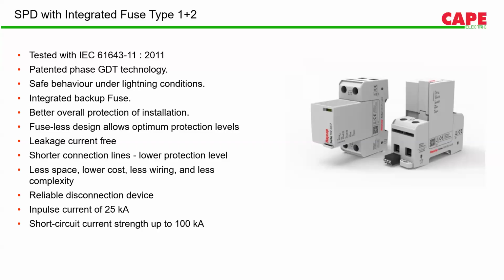That means if we are installing an SPD in the main incomer panel, let's say a 4000 ampere panel, with a fault current rating of 65 kiloampere, in those locations SPDs, with or without backup fuse, shall provide a short circuit rating of not less than 65 kiloampere. Now, unfortunately, most SPDs available in the Indian market have a short circuit current rating of less than 50 kiloampere. So this can create a serious fire hazard during SPD failure.